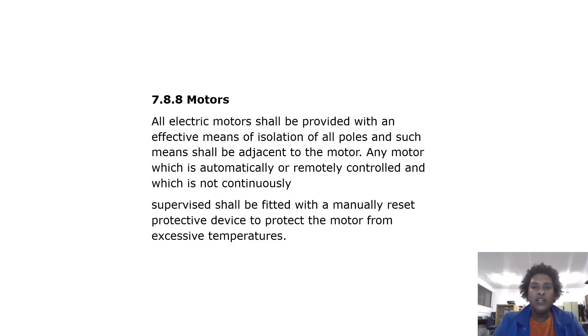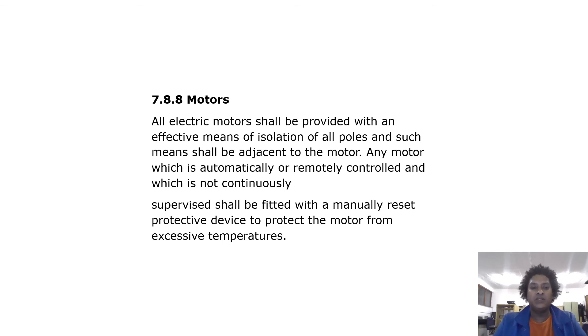Motors: all electric motors shall be provided with an effective means of isolation of all poles, and such means shall be adjacent to the motor. Any motor which is automatically or remotely controlled and which is not continuously supervised shall be fitted with a manually reset protective device to protect the motor from excessive temperatures.